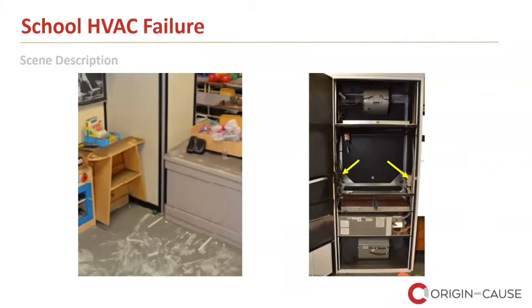So this made everyone really curious - what protected that one room? But once I got on scene, I found it wasn't such a specific room that was protected. It was actually that 18 out of the 26 VFDs were damaged, and it was just by coincidence that 2 of the 8 undamaged units happened to be in one classroom. In this picture you can see one that's significantly damaged and one that is pretty clean.